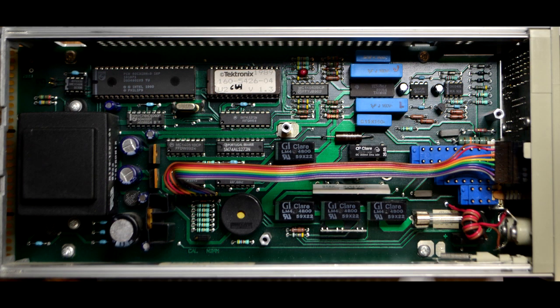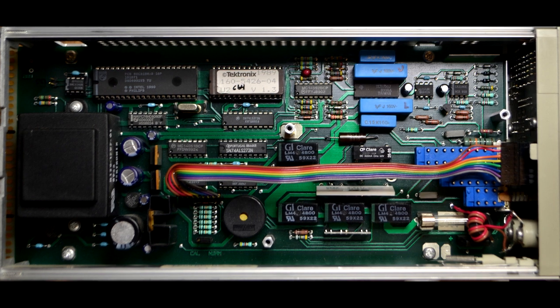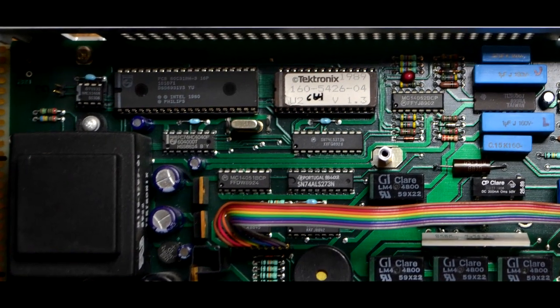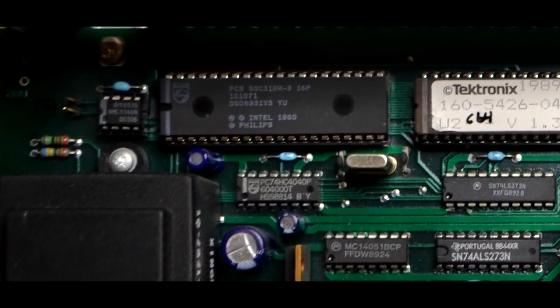Internally, the DM504A is simpler than most other DMMs. The DM504A has 1 large circuit board with no adjustments and a small front panel display board. All control is done by an 80C31 microprocessor with 8K bytes of firmware. All range switching is done by relays controlled by the 80C31. There are no calibration adjustments because calibration constants are stored in an EEPROM, the small package next to the 80C31.